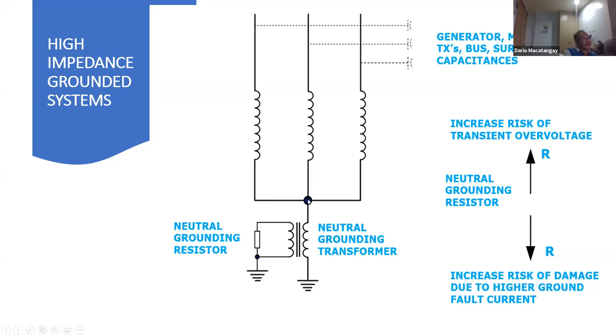Remember though that there are capacitances associated with operation of the generator: the generator, main and auxiliary transformer, bus, and surge arrestor capacitances. Those are imaginary capacitances. You cannot see them other than the surge arrestor, which is there, but they exist. In electrical engineering, a lot of things use imagination to make them work. But you can see that during normal condition, the voltage at this point is very small because there's no fault. Again, this is 100% here and this is 0% here.